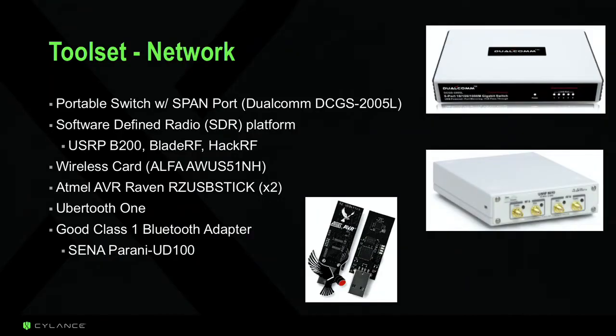On the network side, I recommend a good portable switch with a span port — the Dualcomm switch is about $170, pricey but reliable. Very useful for monitoring Ethernet communication between a patient monitor or infusion pump and the systems it's sending and receiving data from. For software-defined radio, as I mentioned, WMTS and MedRadio bands use vendor-defined protocols, so your best bet is SDR. I use a USRP-B200, very effective. If you have to deal with GSM, that's useful as well.